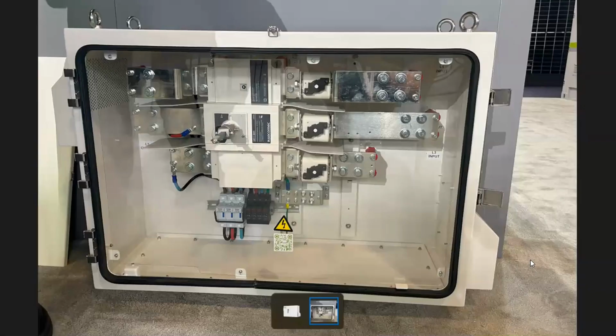And I could probably pull up some pictures and show you the inside of the switch box. So I will share my screen here and show you a little bit of the switch box. These are some pictures from when we showed this product at RE Plus in Las Vegas back in September. And this is a disconnect switch with 1,000 amp fuses and bus bars that accommodate the conductors for combining the inverters into a single output circuit. This product was listed to the UL 1741 standard with 3 275 kilowatt inverters.